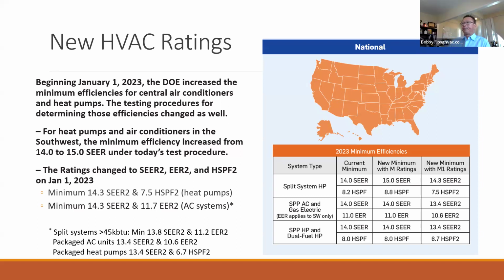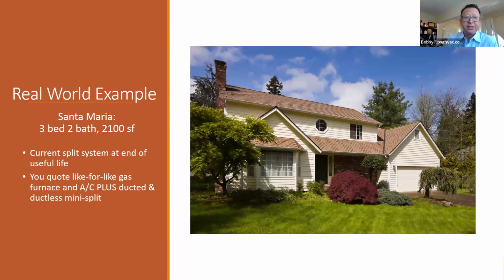Okay. But there was a question in chat, Bobby, about rooftop heat pumps. It's important to distinguish between those standard variety heat pumps and the variable capacity heat pumps we're more focusing on. Now I do see that the inverter compressors are making their way into rooftop units. So the Infinity type of equipment, the highest tier of rooftop, they will be changing over. So we'll see more of that versus a standard on-off scroll compressor. That's great. So we'll be seeing those changes.